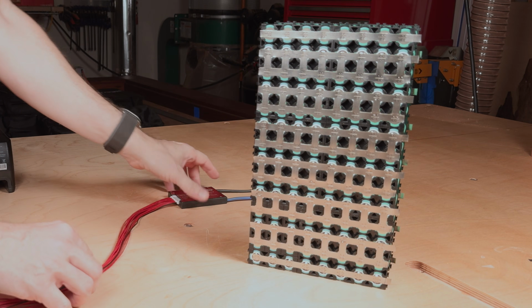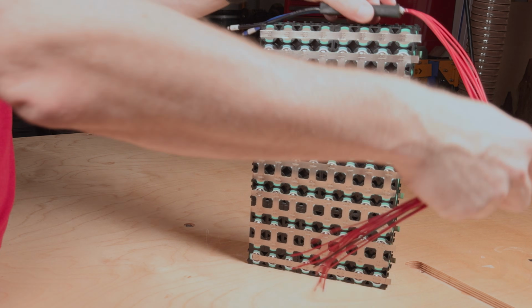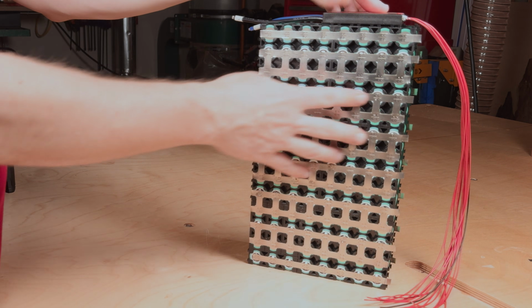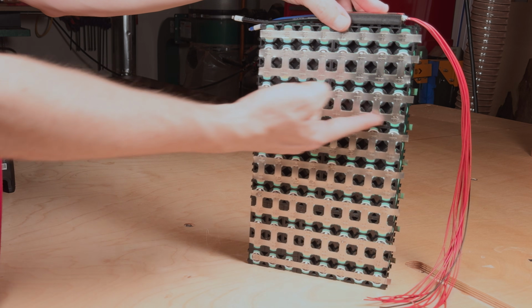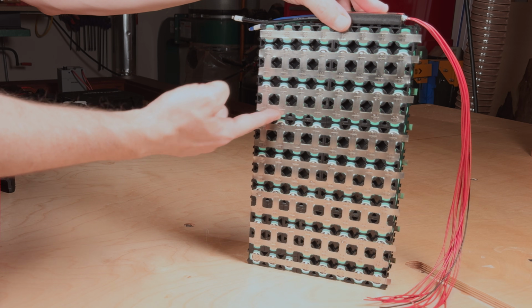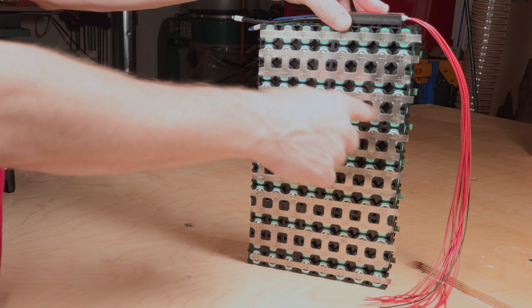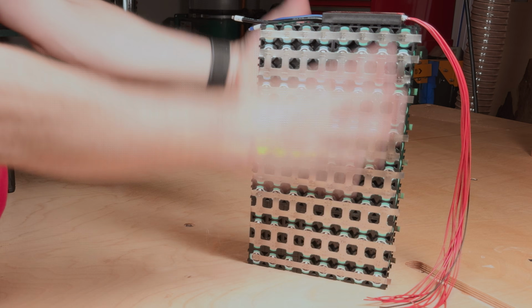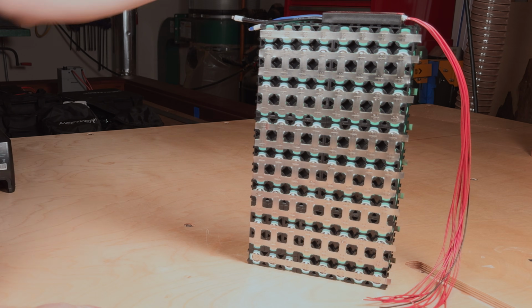That lets the BMS do something called balancing, where it balances the charge between each of these rows. After a lot of charge-discharge cycles, one row could be at 4.2 at maximum charge, and another at 4.1. Ideally you want everything at 4.2, so this allows it to monitor each row and bleed off some voltage here and there to make sure everything gets charged up to 4.2.